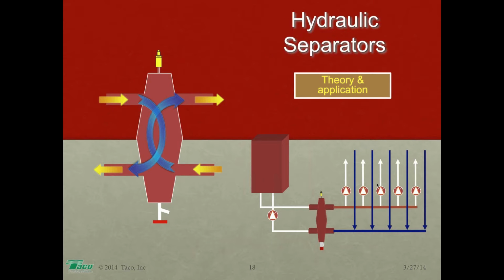All righty. Cool. Let's talk about hydraulic separators now. We talked about hydraulic isolation and the importance of it. And we had a question earlier that beautifully illustrated why hydraulic isolation is so critically important. The distribution flow rate will very often, if not always, be greater than the boiler flow rate. How are we going to keep those two from messing with each other? Short fat headers is one way. Building your own short fat header is a very, very good way of doing it.